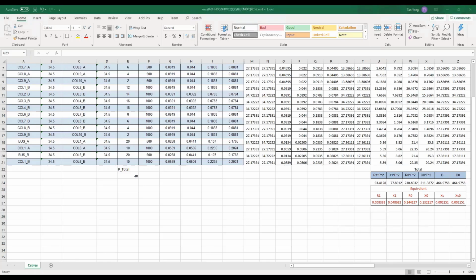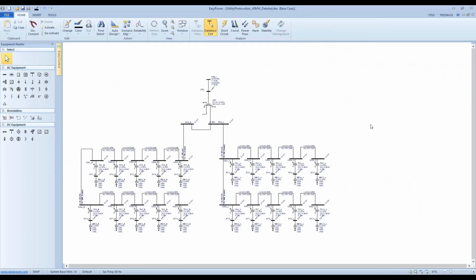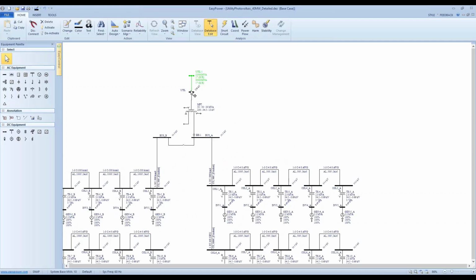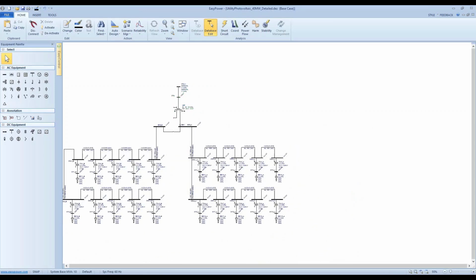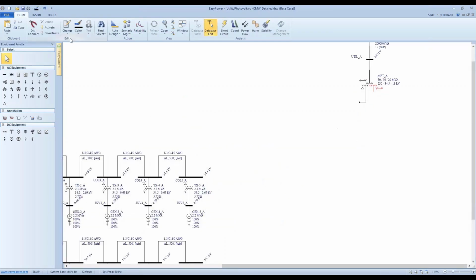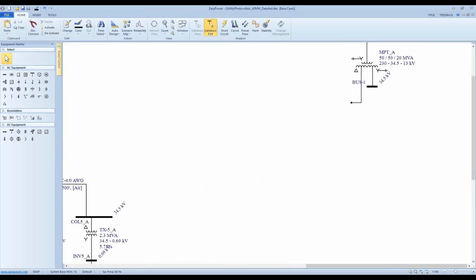And what we need to do next is to build my equivalized model, the lumped model, and run the power flow study and the short circuit studies to compare the results between the one-line model and the lumped model, equivalized model, right? So what we do here is copy utility bus and the main power transformers because I don't equivalize them. I only equivalize equipment downstream. So they are the same. Now I put a bus here, 34.5, put another bus down below, put a cable, which is my collector system equivalent between them. I should connect from here.